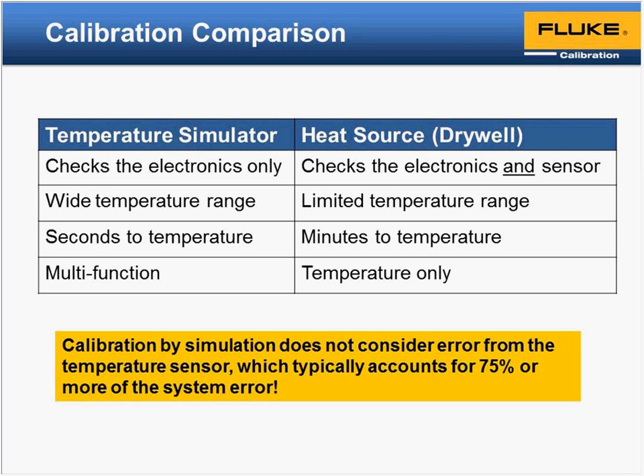So, by comparison, we're going to look at the base simulator side, then a heat source side, and then we're going to look at a heat source with a reference. Some of the things to remember as you're going through things with just a simulator: electronics check only. The good thing about those is they give you pretty much unlimited temperature range, because most simulators will be able to simulate most RTDs and thermocouples, since you have quite a wide range and a variety of different types of sensors. The thing about them is it's pretty much instantaneous. It's just seconds to simulate that. And we mentioned it's multifunction, so you could have PRTs, thermocouples, things like that.